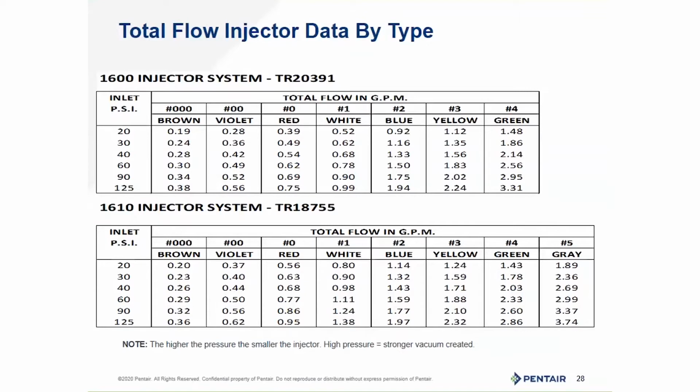In a residential application, the customer's not necessarily going to notice a difference. But if you're using that in a commercial application for high purity water pretreatment, over time you could lead to fouling membranes because you're not getting good resin regeneration long term. And with the volumes of water used in commercial applications, that can show up a lot quicker than in a residential application.